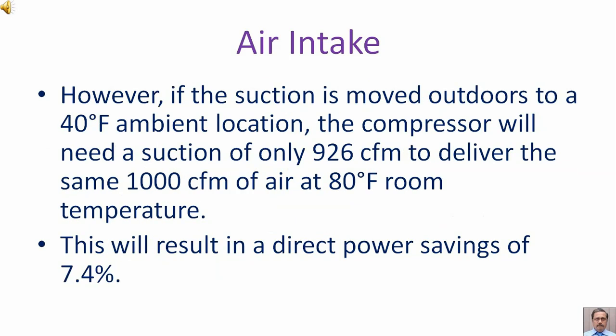However, if the suction is moved outdoors to a 40°F ambient location, the compressor will need a suction of only 926 CFM to deliver the same 1000 CFM of air at 80°F. This will result in a direct power saving of 7.4%.